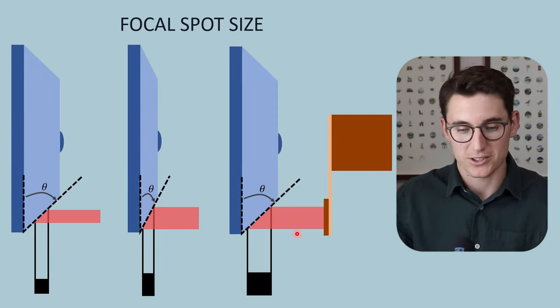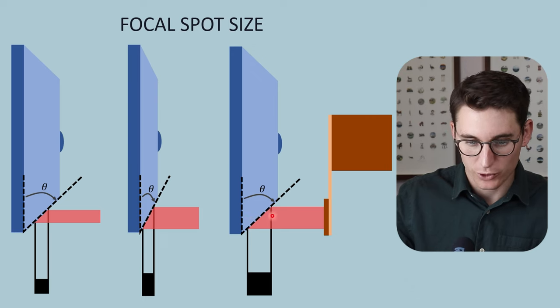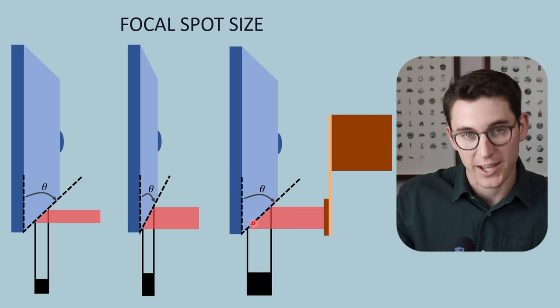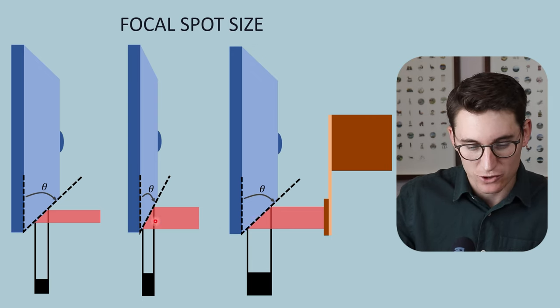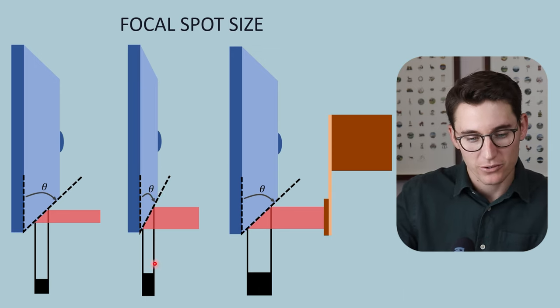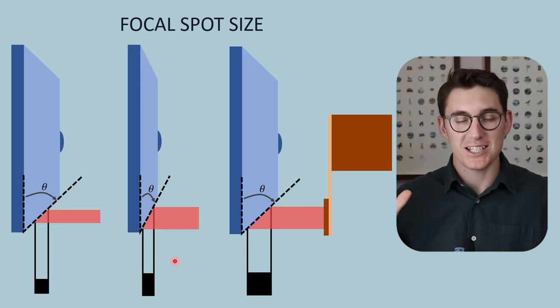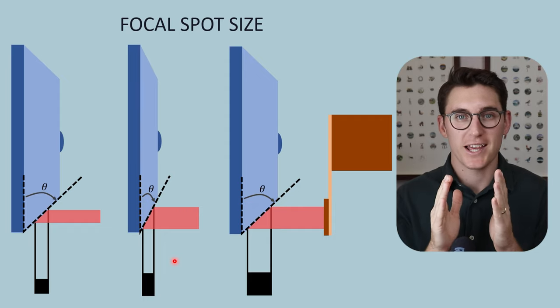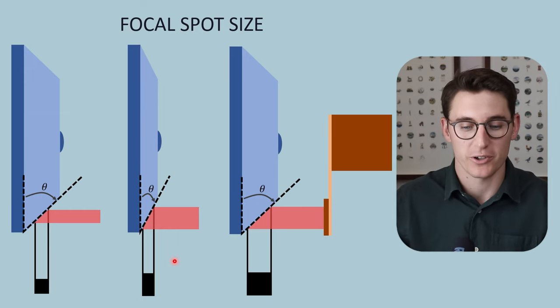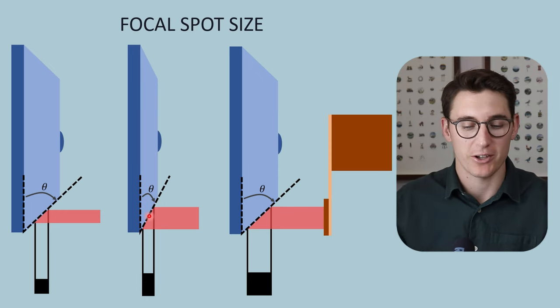Looking at this practically: on the right we have our electron beam making our actual focal spot and giving us our effective focal spot at a specific anode angle. If we take that same electron beam but reduce our anode angle, we can see how we have narrowed our effective focal spot. In a future talk on geometric blurring, you'll see why a small or narrow effective focal spot is important for creating sharp images with good spatial resolution and little geometric blurring.